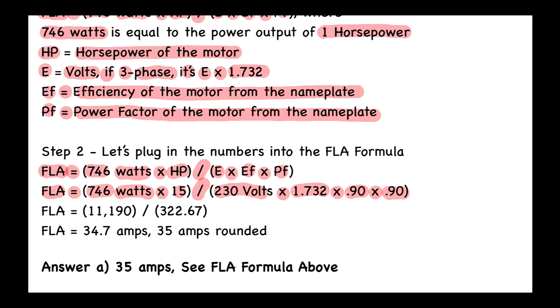Let's take it down to the next line. FLA is now equal to 11,190 divided by 322.67, so the FLA is now equal to 34.7 amps, and we're just going to round that up to 35 amps.